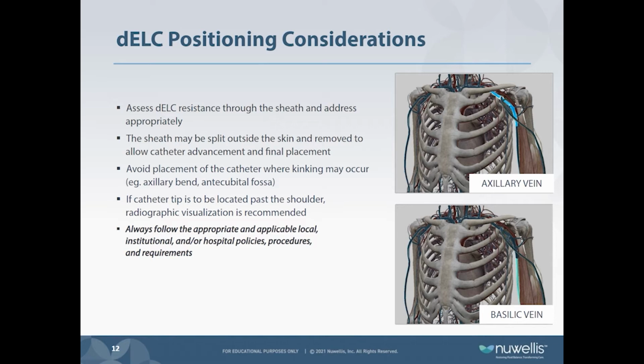Visualization of where the catheter tip will reside is especially important with Aquadex therapy, as that is where the withdrawal and infusion of blood is occurring. During placement, assess resistance to help determine the optimal position. The introducer sheath may be split outside the skin and removed to allow catheter advancement and placement. Avoid placement of the catheter tip where kinking may occur, particularly in the axillary bend.